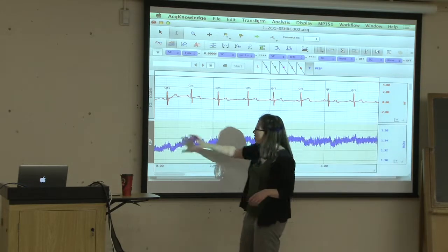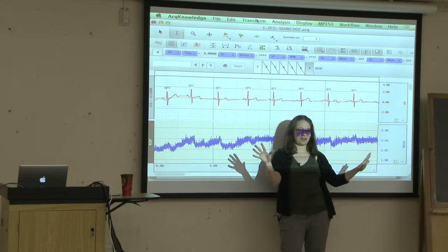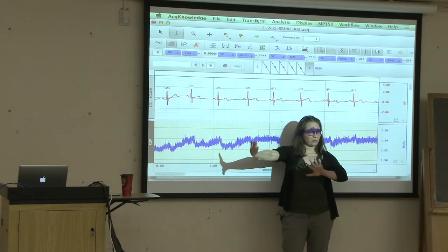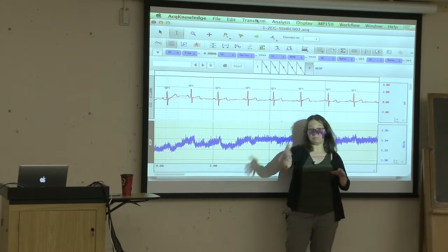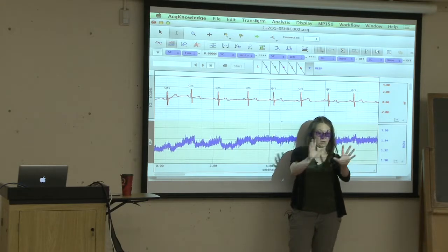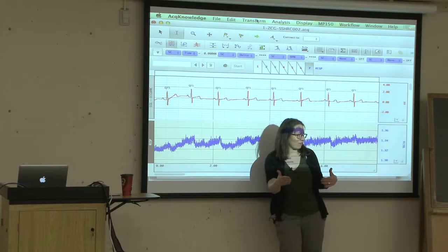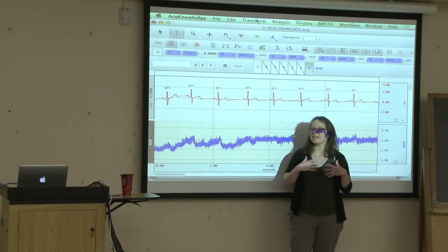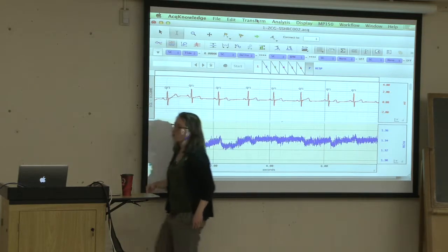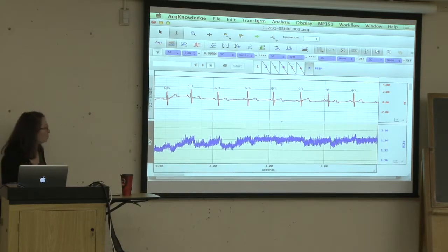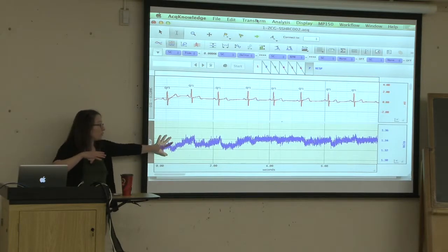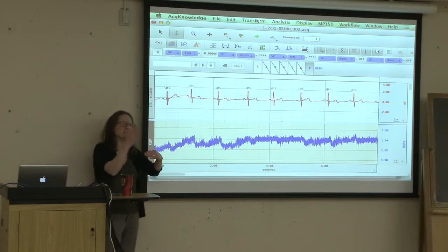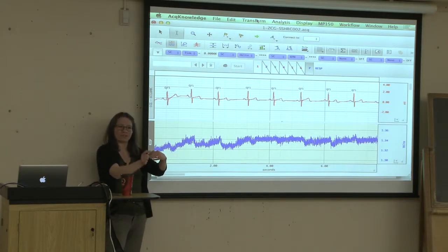The raw impedance measure has all sorts of waveforms contributing to it. However, if we filter out every period contributing to this complex wave that is above 0.5 hertz, then the only thing left in the Z0 band is respiration. So we want to cut off every part of this waveform that is more frequent than 0.5 hertz. Hertz is the number of cycles a second, so this would be half a cycle in a second.